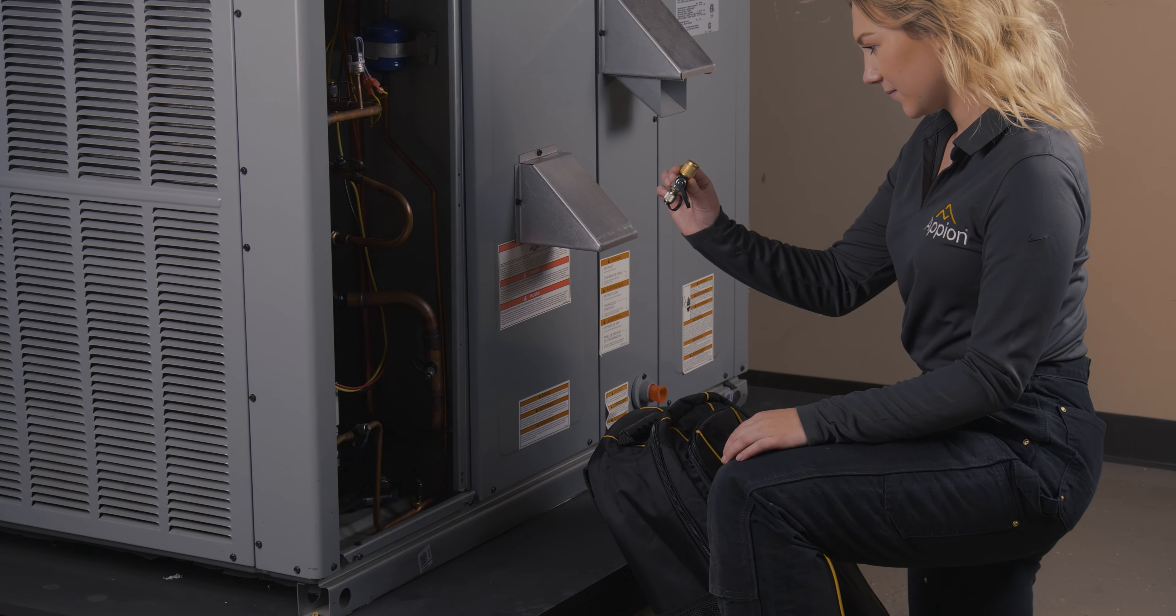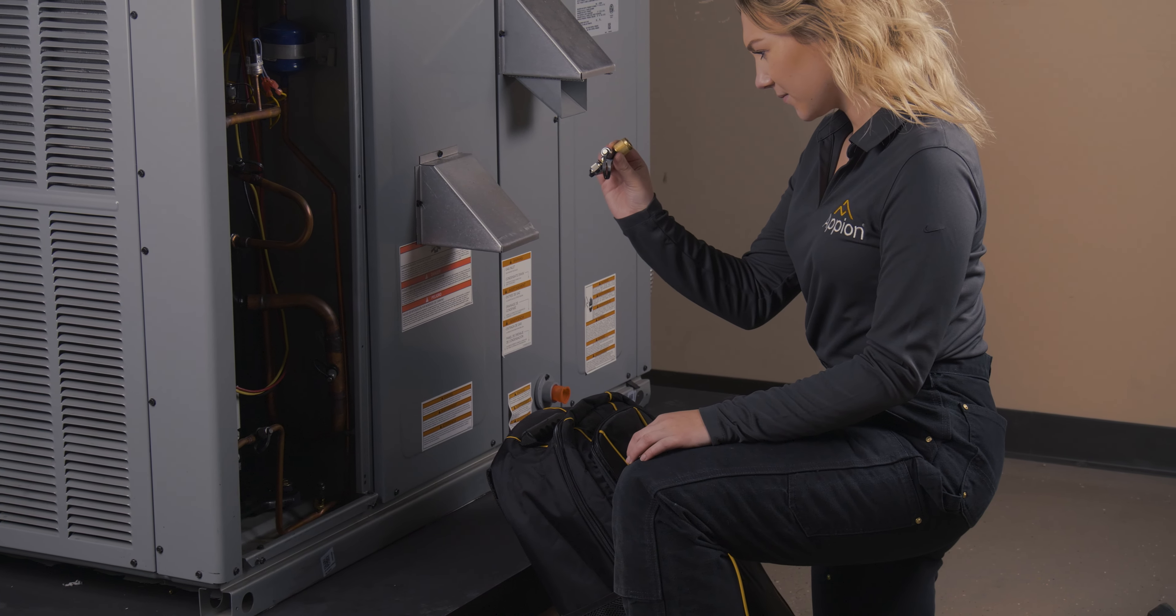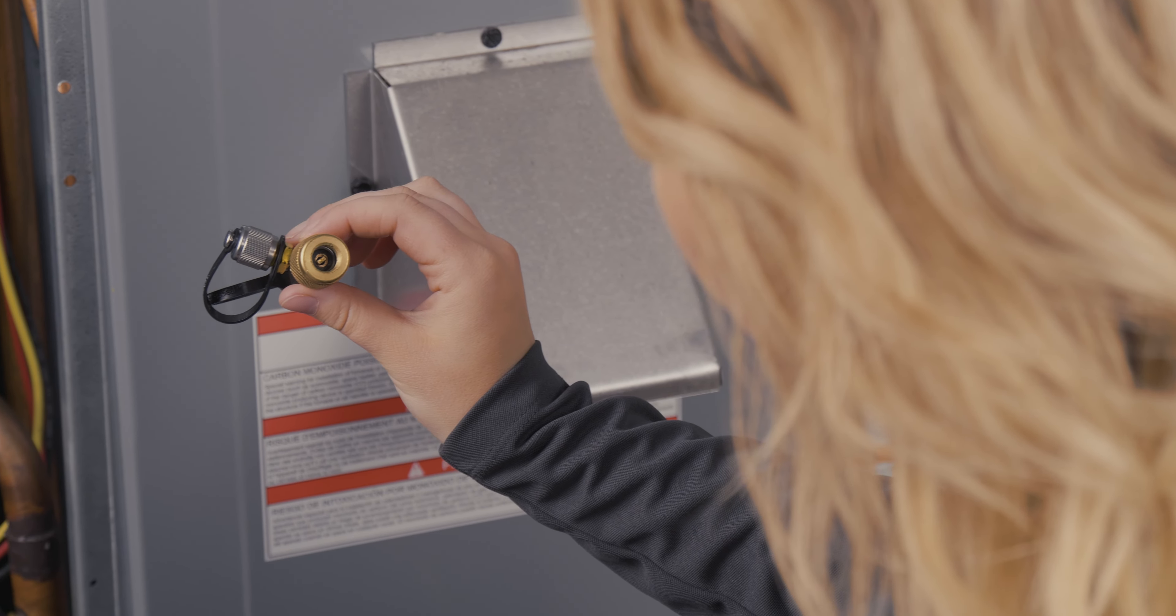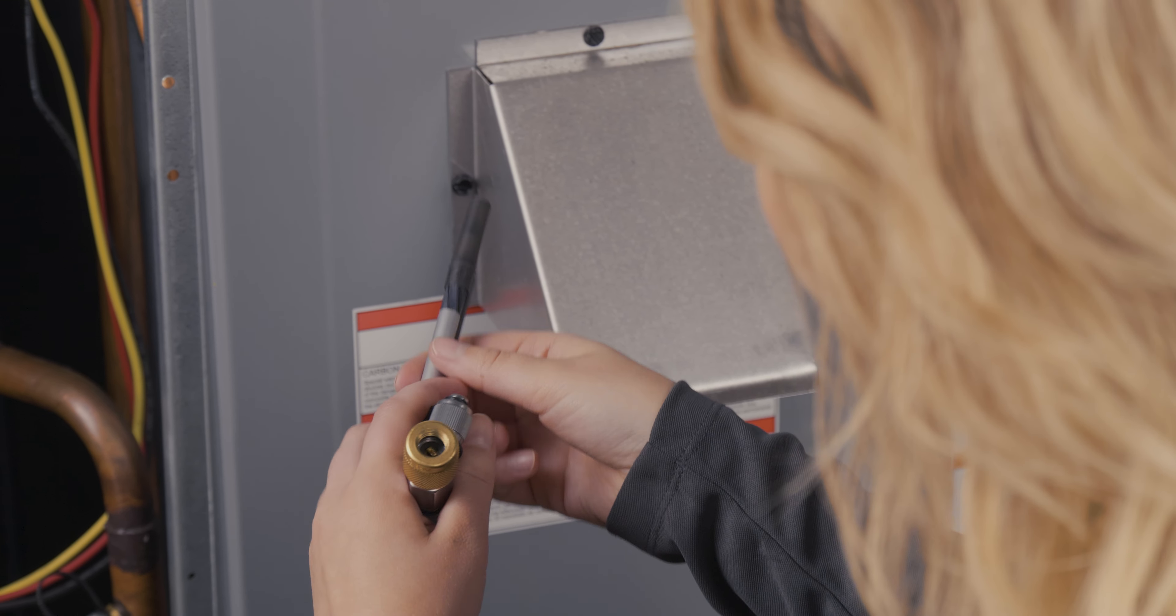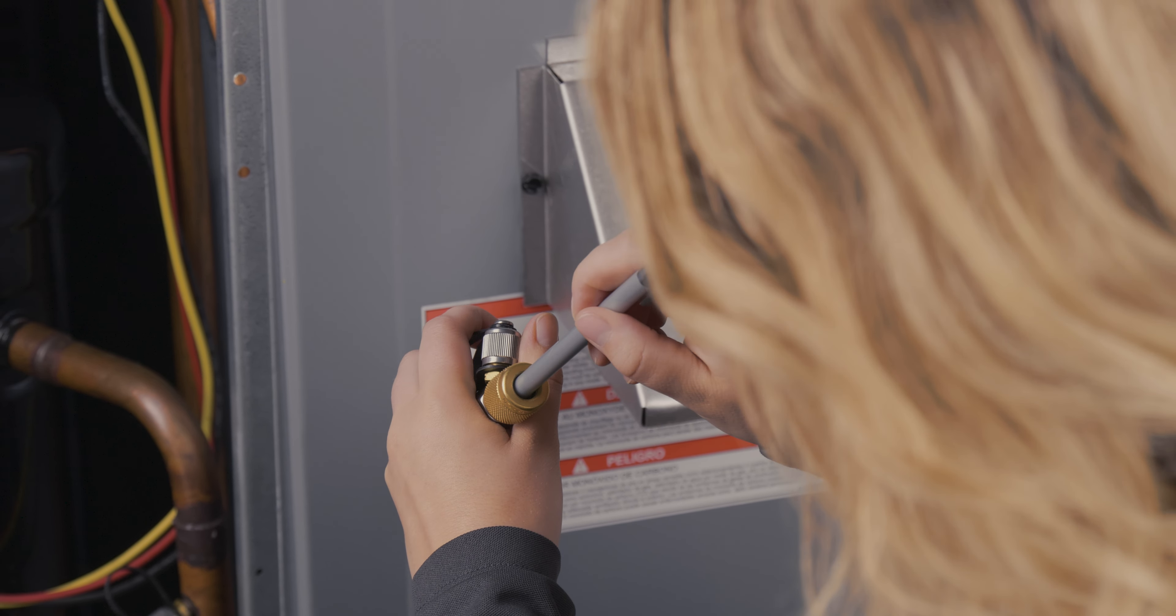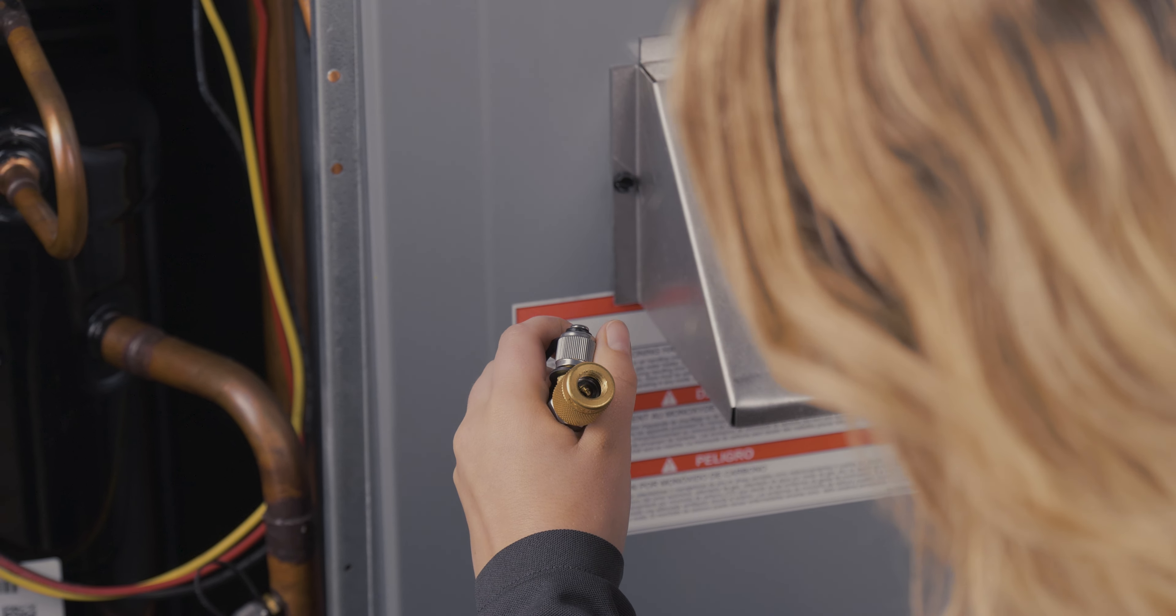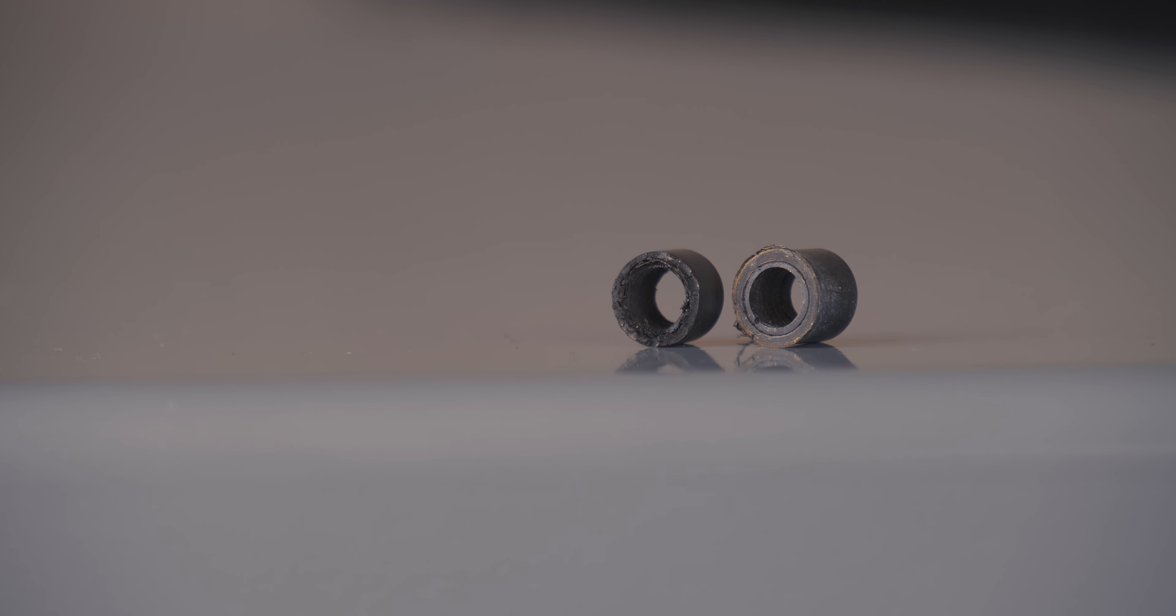Check the gasket condition and ensure that the gasket is fully seated in the swivel fitting connector. If the gasket isn't fully seated, use the blunt end of a ballpoint pen to fully seat it. Damaged or degraded gaskets should always be replaced before service.